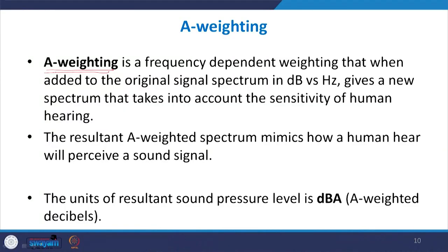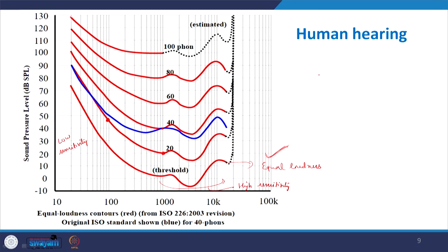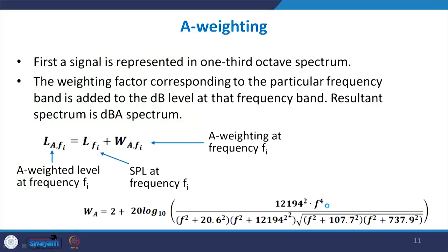Because human hearing is highly frequency dependent, whenever a spectrum is obtained it is shown as dB versus frequency. We apply a filter to these dB levels called A-weighting — the most common filter in noise control applications. This filter subtracts levels at low frequencies (the low-sensitivity region), applies small adjustments in the mid range, and adds levels at high-sensitivity regions, to mimic how the human ear actually hears.